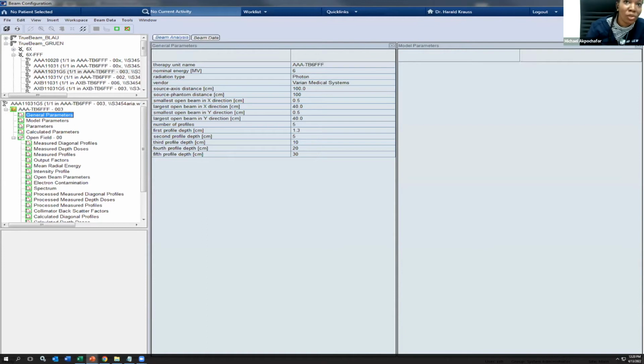In our center, we used 2 weeks, and that is the fastest commissioning so far. But those 2 weeks were not just 2 weeks of day. They were 2 weeks of both day and night. We actually use days and nights for our commissioning, about 2 weeks in total for the commissioning process. So all this takes a lot of time, because you have to do this for each of the algorithms, the treatment planning algorithm. Then also you have to do it for each of the energies and each of the field sizes. So you can imagine trying to process all this data for one energy, for each of the algorithms and everything. So that is why the commissioning process actually takes a lot of time.